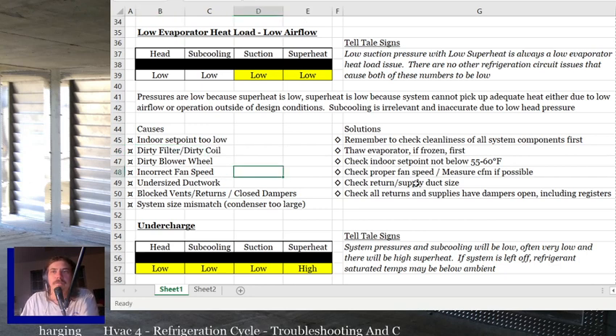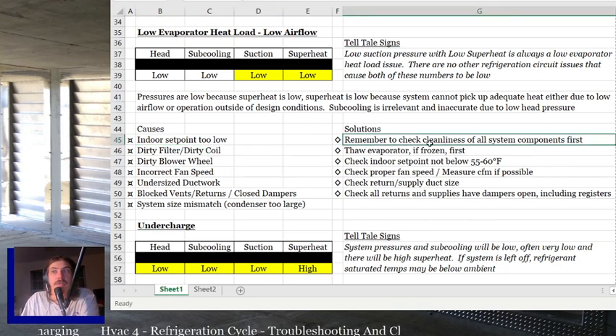to the outdoor unit. The solutions to that are: check the cleanliness of all your system components first. Remember, if you suspect a problem in the system, the first thing you should be doing anyway is checking that your filter's clean, your coils are clean, your blower wheel's clean, everything looks good, because you can't diagnose anything if all that stuff's wrong. All right? If the evaporator's frozen, so you get there and that whole line is frozen and the evaporator's frozen, the first thing you have to do is thaw it. Can't do anything else to the thing frozen. You can't diagnose it while you've got no airflow.